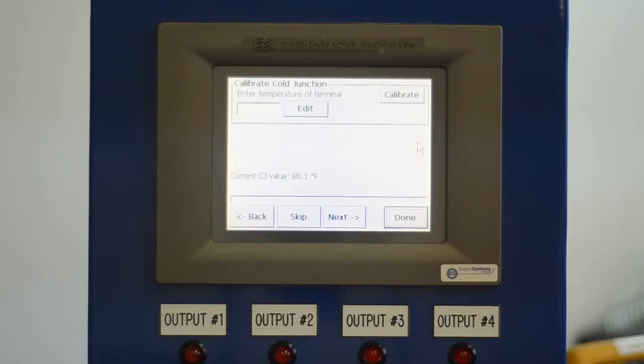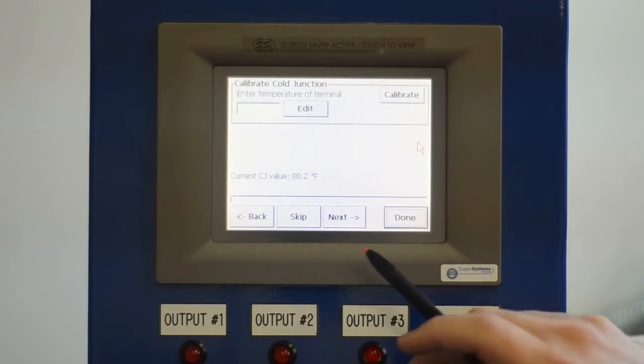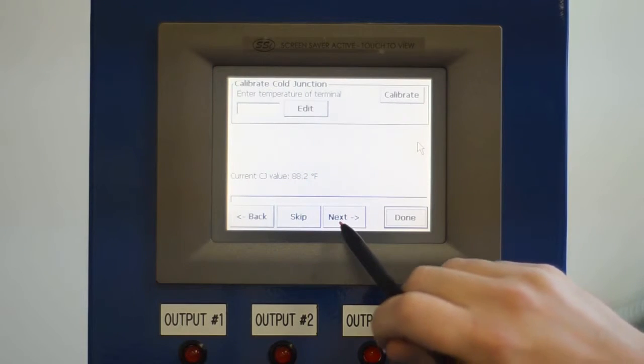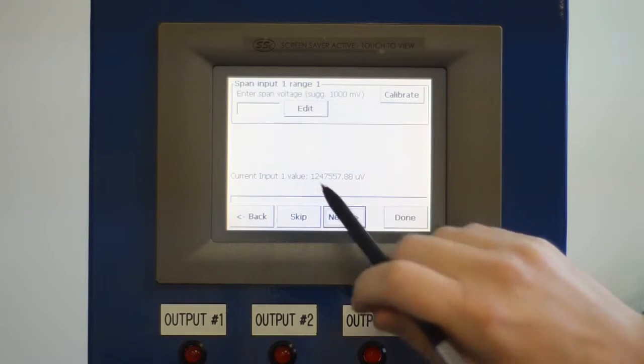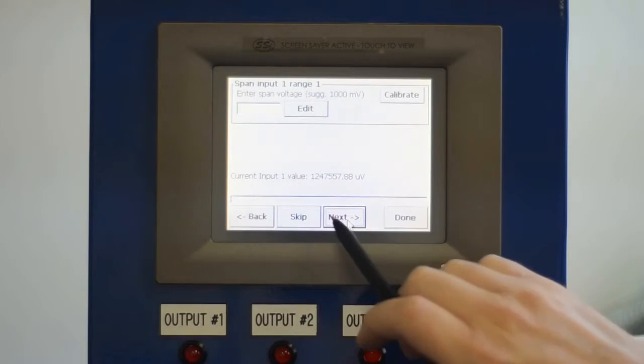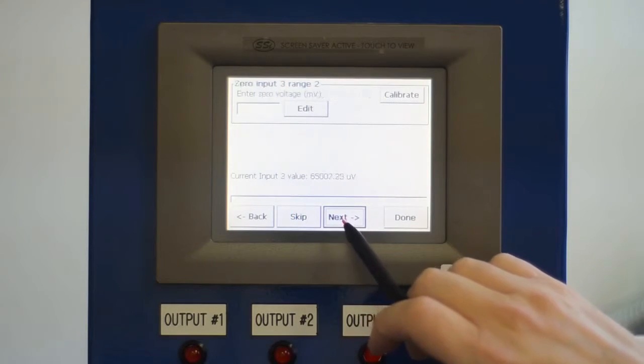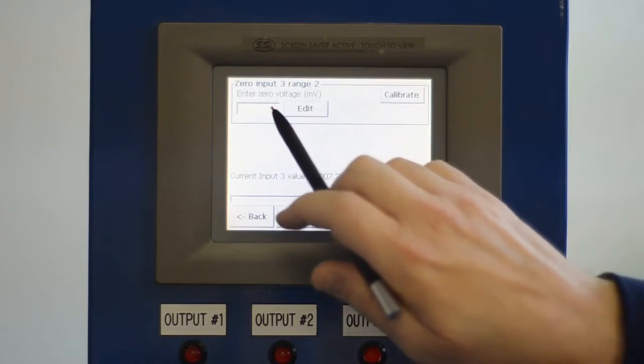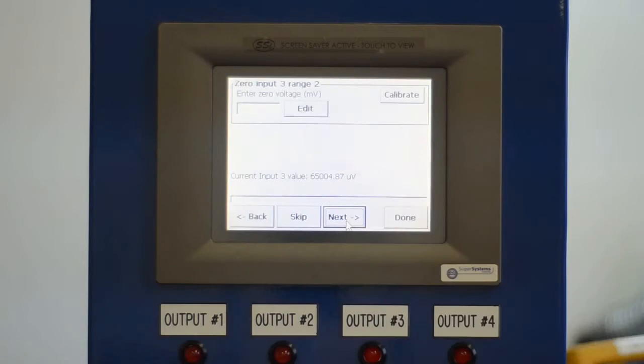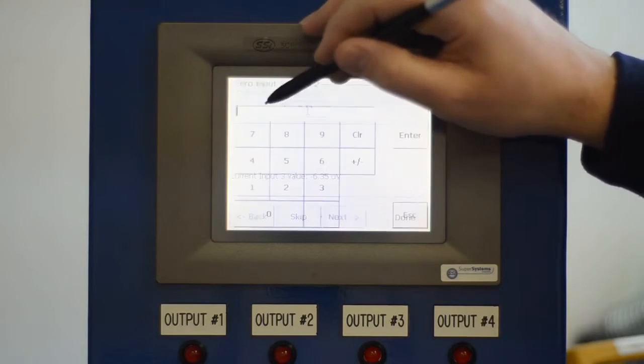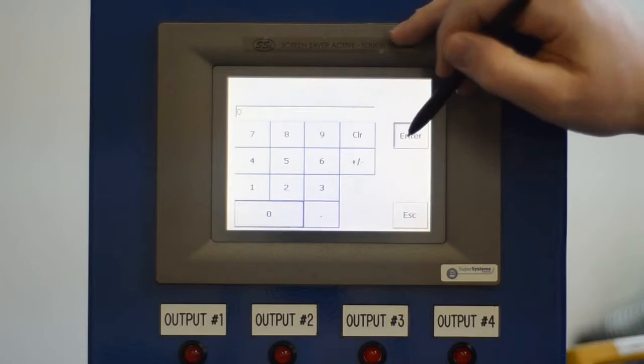We will not do the cold junction first, but what we will be doing is input 3, which is terminals 27, 28. So we have to select next until we see up here it's going to tell us our 0 for input 3, range 2, and this is our 0 millivolts. At this point we're going to source in from our sourcing meter 0 millivolts into terminals 27, 28, input 3. We're going to edit this field and tell it what we're sourcing in.